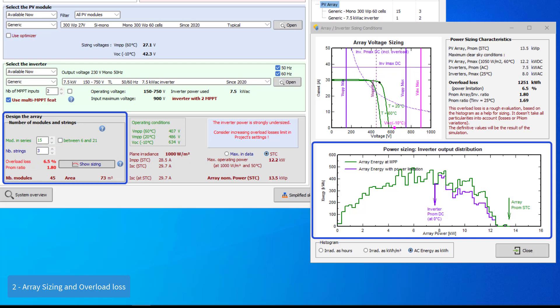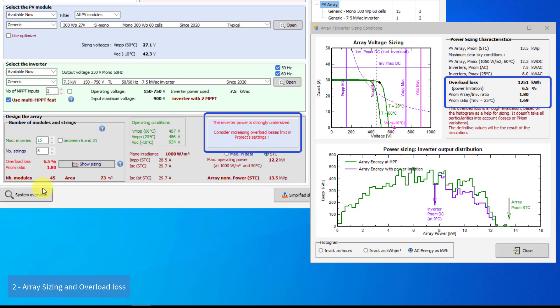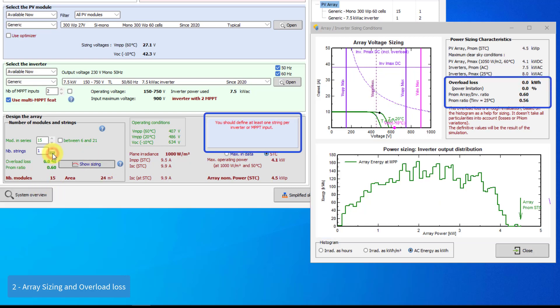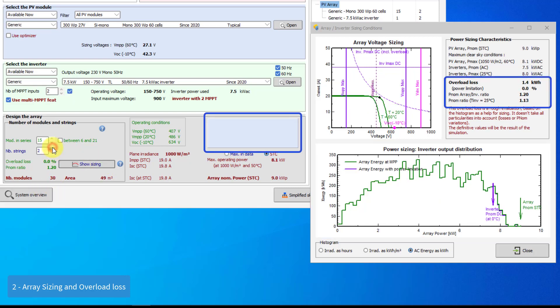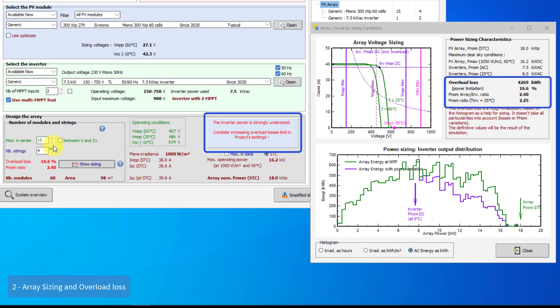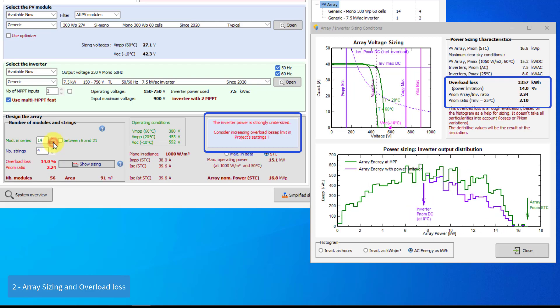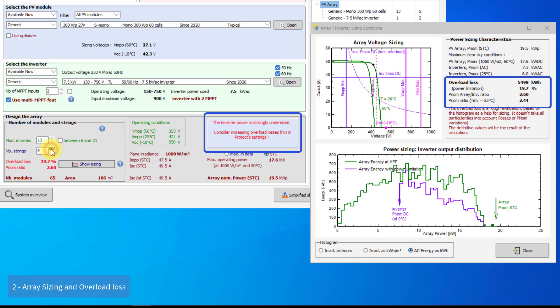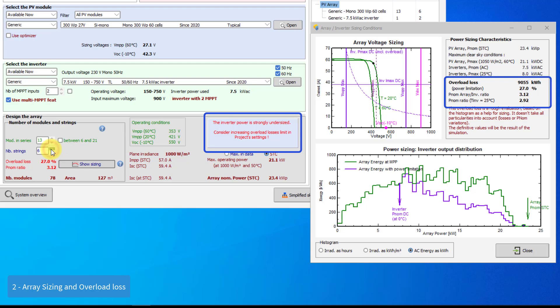The difference between these curves represents the overload loss. The area between these curves with respect to the full histogram area is the overload power loss percentage. PVSYST considers your sizing to be good when the overload loss doesn't exceed 3%.